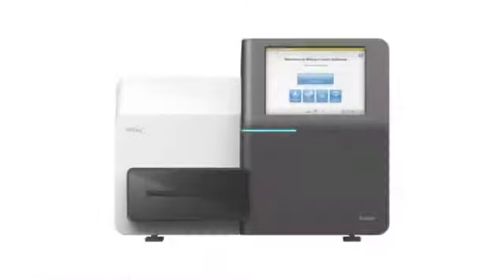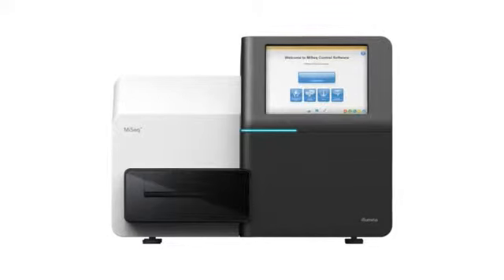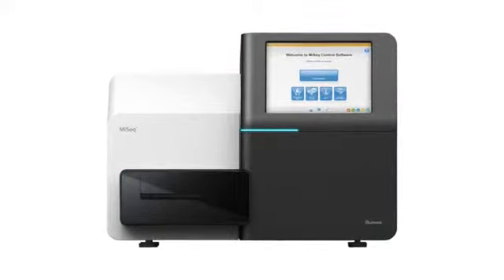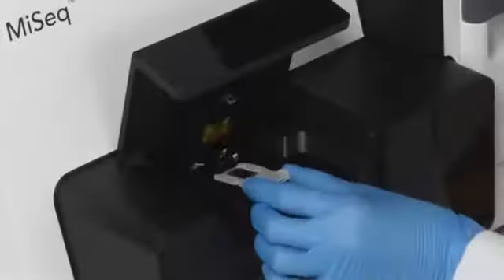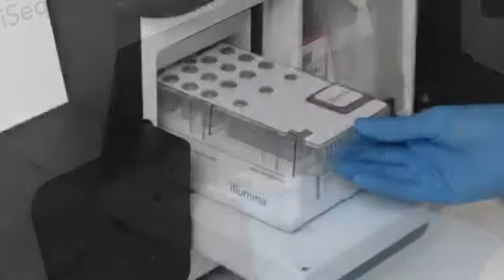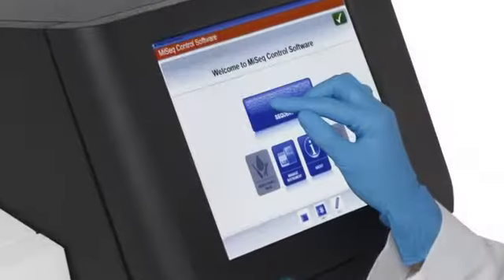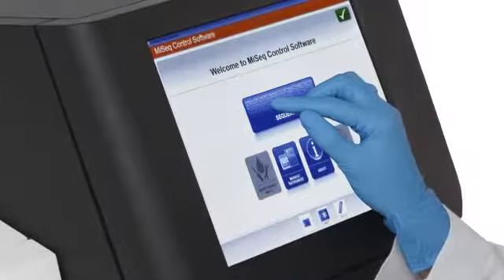Operating a MiSeq is both simple and intuitive. If you look at the form factor of the instrument, all of the black areas are the areas that a user would interface with. There's a logic flow to where the flow cell is located, where the fluidics and reagents are located on the bottom right of the instrument, and the touch screen interface up on the top right.